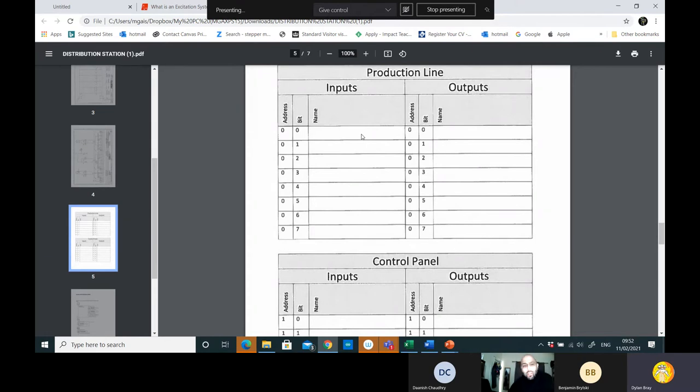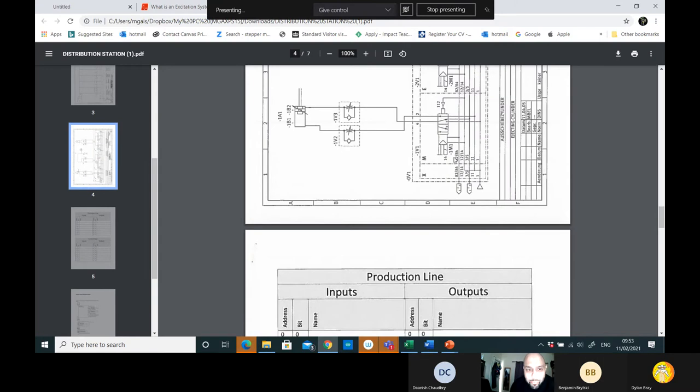There are other ways too. When it comes to outputs, it's harder, so we force outputs to switch on. We have a device we can connect, where we switch outputs on, and then you can see which outputs switch on. Then you can write on here which outputs switch on to which particular port number on the PLC. So then you've got your tag table in there as well. So that's done. Then you can start doing your program.